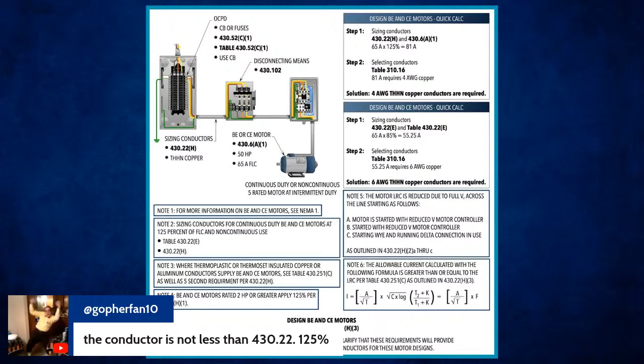Now, when I was out teaching, I would give them code loops they write in their book, and I'd tell them right there at that table, if you're sizing conductors, write that down. Go look at 430.22 for a single motor, and 430.24 for multiple motors. When sizing your overcurrent device for a single motor, we're looking at 430.52(C). If you're doing one or more motors, you need to look at 430.62. We're doing one motor, so we're going to look at 430.52(C)(1). Right there, it says to start, you cannot exceed the value calculated. So that's where I establish a minimum requirement as a starting point.